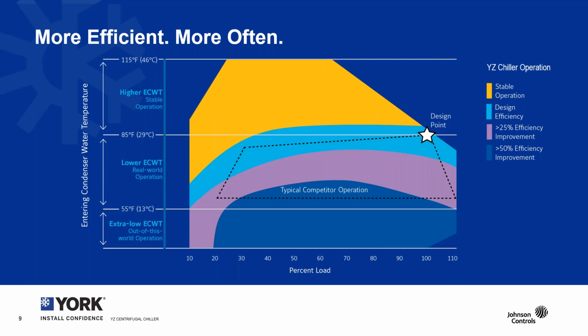And the lower end of that map represents entering condenser water temperatures even below that which is factored into the IPLV part load formulas that you compare chillers against, running below 65 and below 55 and down to 40 degree Fahrenheit entering condenser water temperatures. It creates incredible levels of efficiency at those operating hours, which are many in many parts of the world. This chart even demonstrates that 40 degree entering condenser water can be lower than the 44 degree leaving evaporator water temperature, and we call this inverted operation. This great portion of the operating map gives you not only great efficiency, but the ability to offset water side economizers and reduce cost and complexity of your systems.